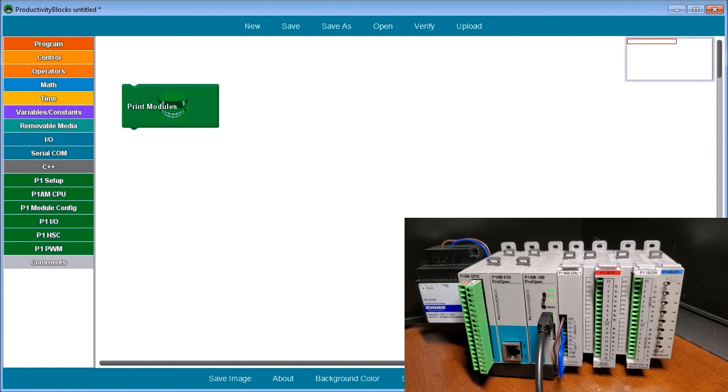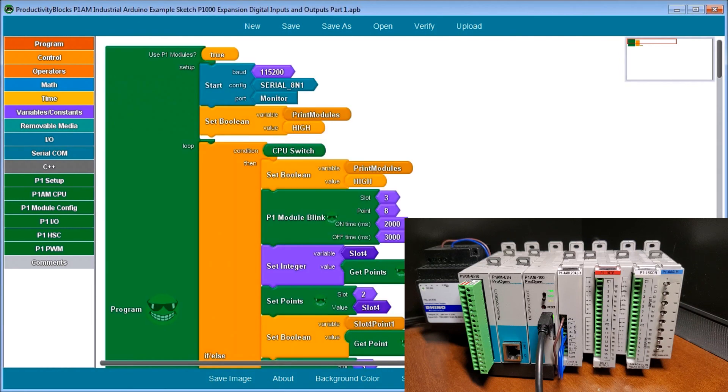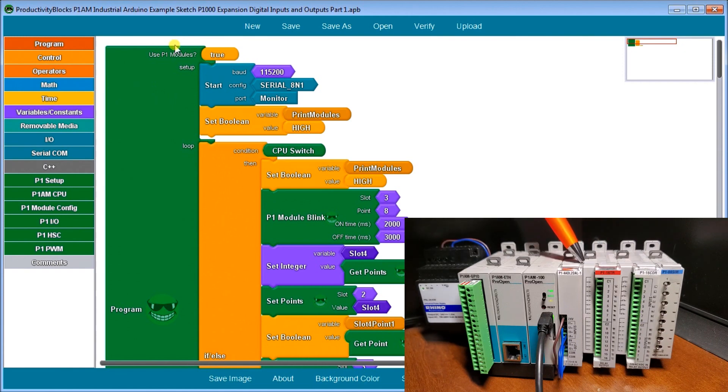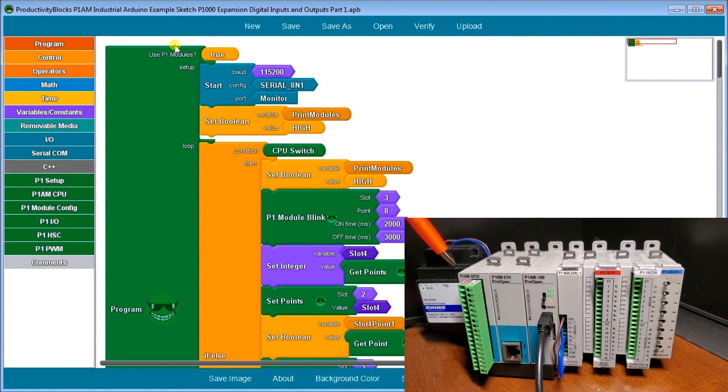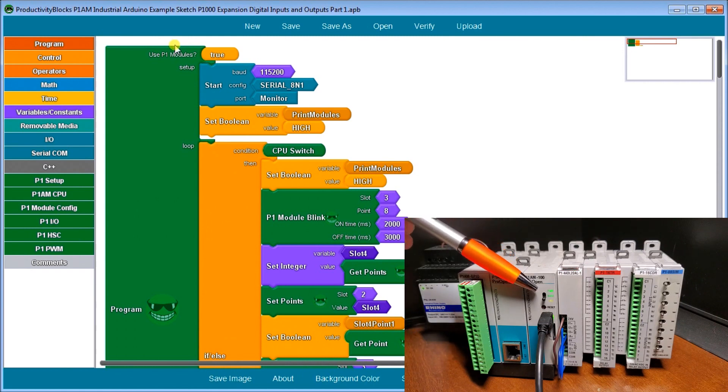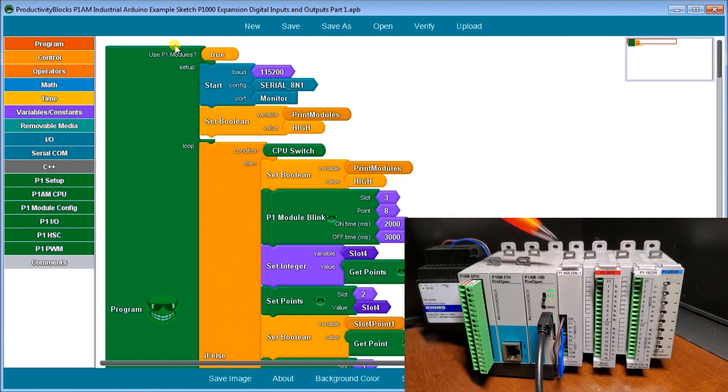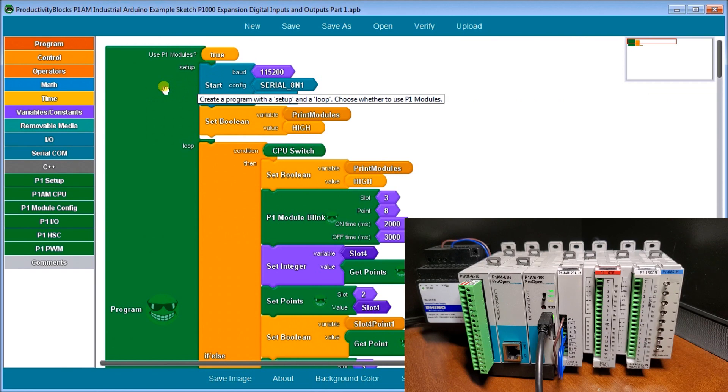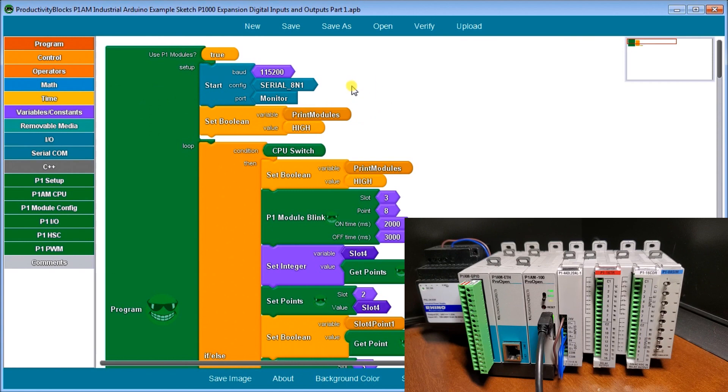Now let's look at a sample program. The first thing we do is set our P1 modules to true, meaning we're using the back plane and powering up these digital IO cards from the back plane. It takes an external source of 24 volt to power those up. Then we start and set up our serial monitor at 115,200 baud, serial 8 none 1, monitor port. We set a boolean, print modules to high.